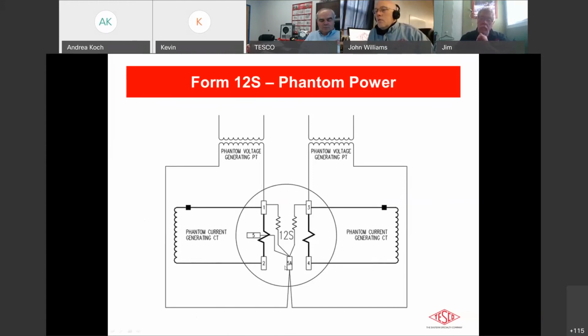Other than the thing that you have to make sure of in the application in the wiring is the 12S has the neutral connection either at the 6 o'clock or 9 o'clock position. A lot of irrigation wells in Texas are using the 12S meter. Yeah, also very popular in high-rise condominiums where you have a three-phase four-wire supply to the building, but each condominium or apartment, if you want to call it that, is a 208 supply.